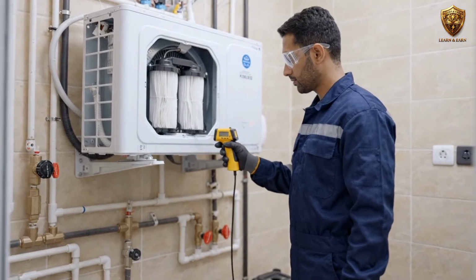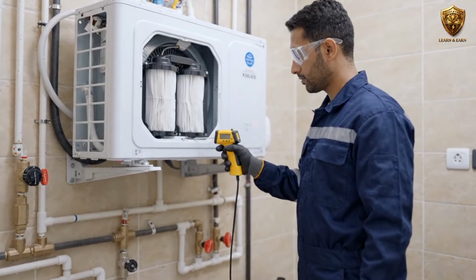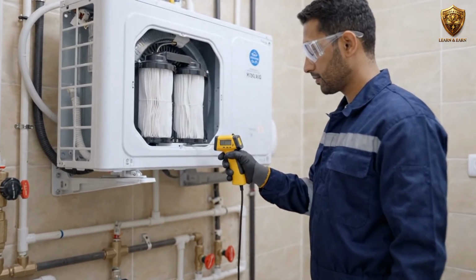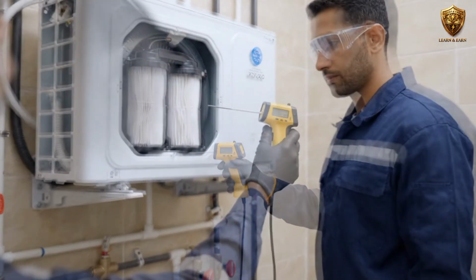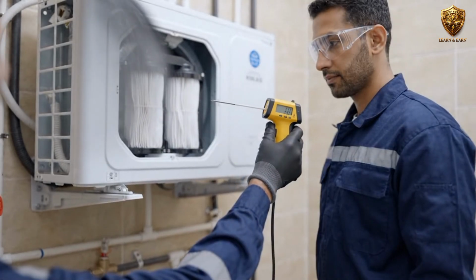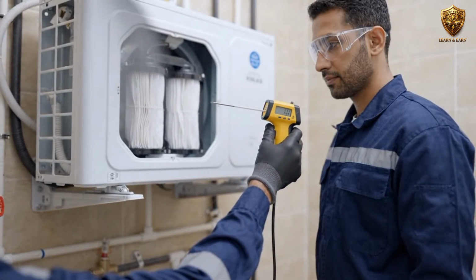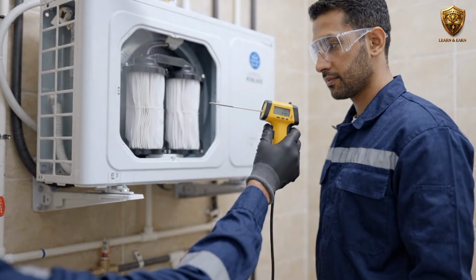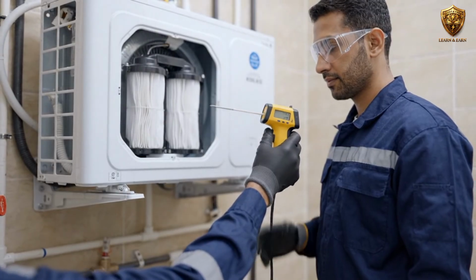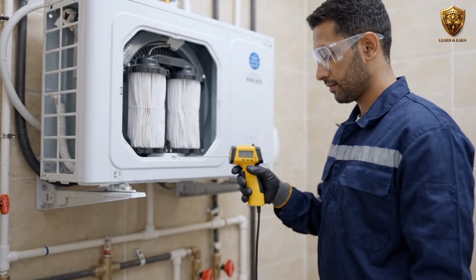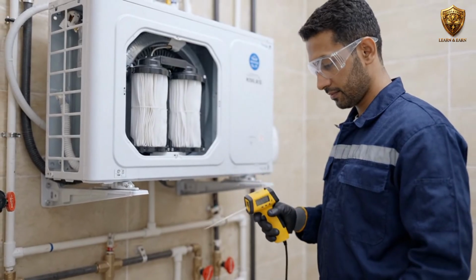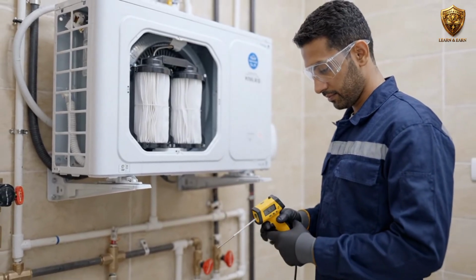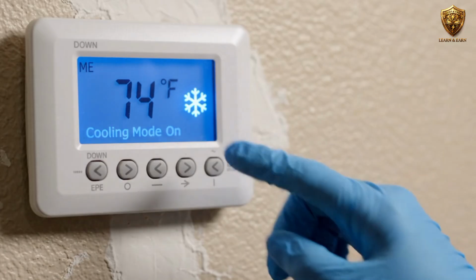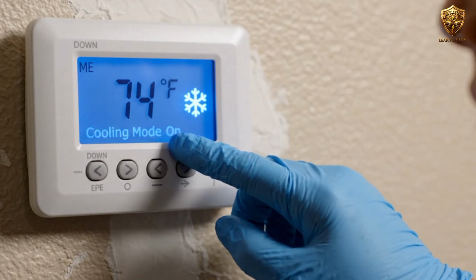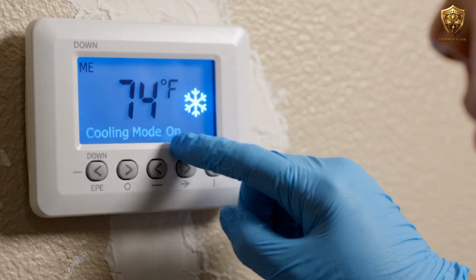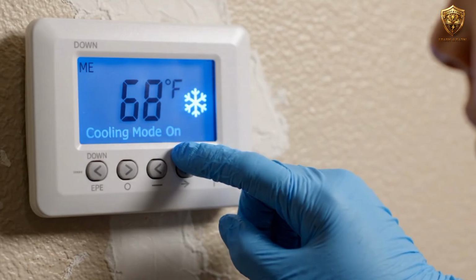The first thing to understand is the difference between not cooling and not running. If the indoor blower is running but the air coming from the supply vents is close to room temperature, the outdoor section may not be operating correctly, or the refrigeration system may not be producing enough cooling. If the indoor blower is not running at all, the fault can be somewhere else, such as the thermostat, control circuit, blower motor, capacitor, control board, or power supply. This simple observation already gives the technician useful information.